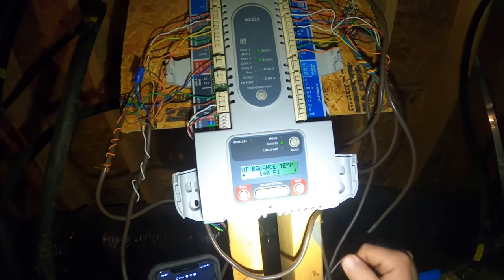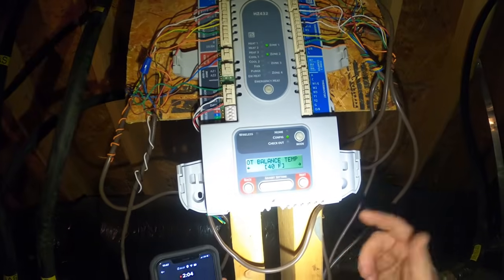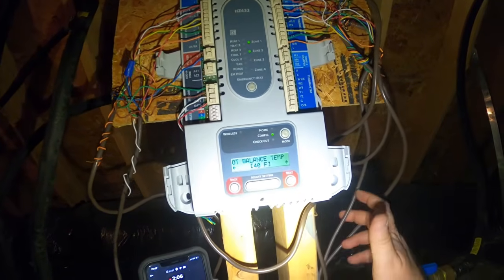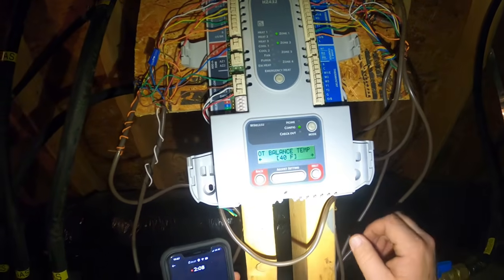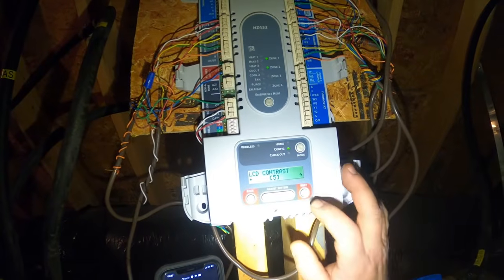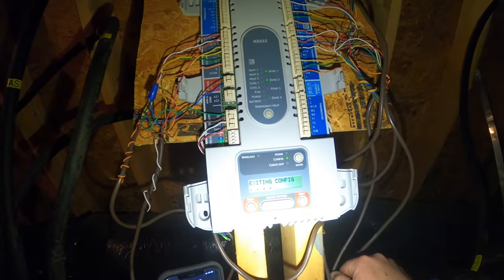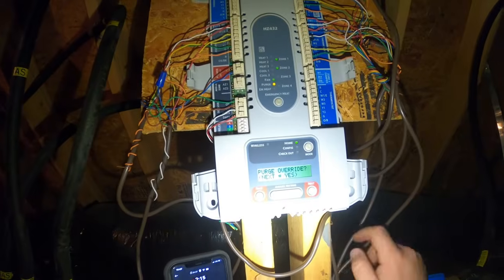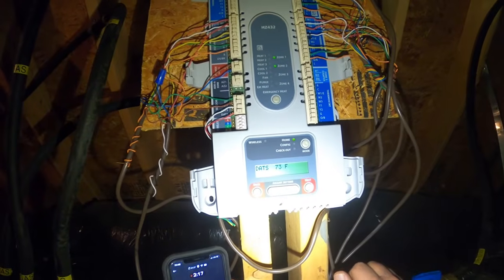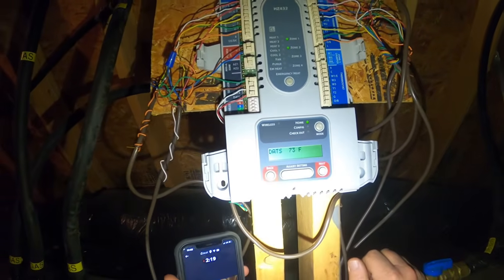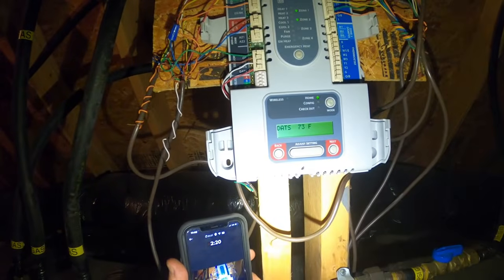And then outdoor temperature balance, we're going to set that at 40 degrees. So that's going to be our lockout. Below 40 degrees, it's going to run the furnace. Above 40 degrees, it's going to run the heat pump. We are good to go. That's our purge. That's why you hear the blower coming on. We're going to cycle that off.